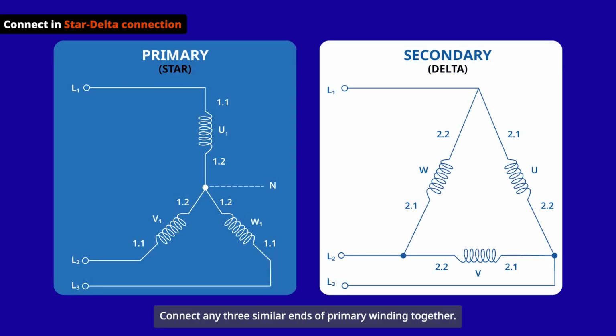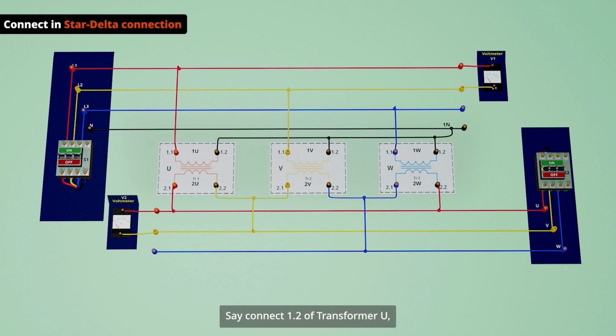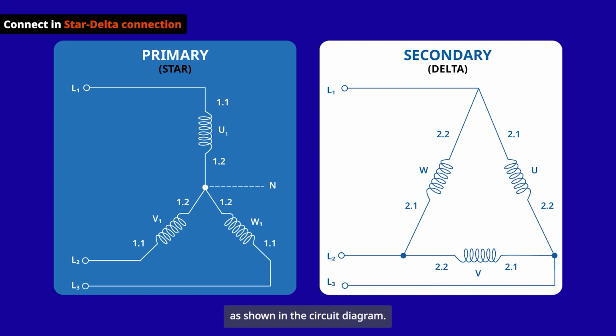To connect in star-delta connection, connect any three similar ends of the primary winding together. Say, connect 1.2 of transformer U, 1.2 of transformer V, and 1.2 of transformer W together and mark the junction as 1N, neutral, as shown in the circuit diagram.